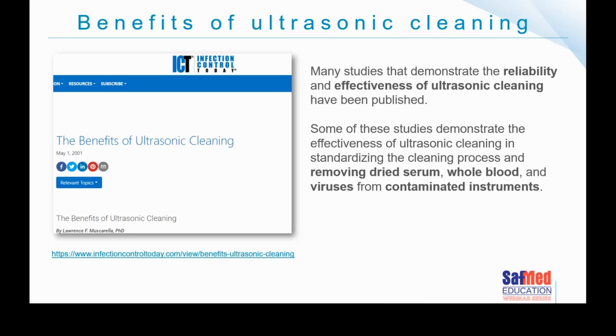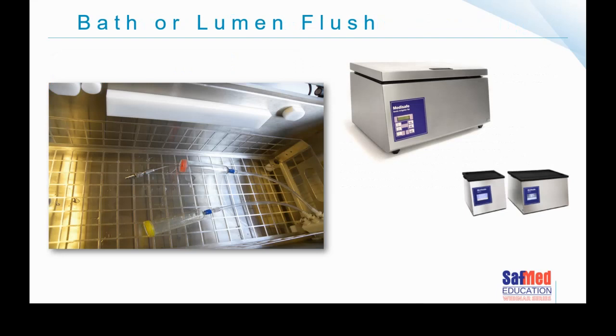I find that ultrasonic cleaners are probably one of the most underused pieces of equipment in the CSSDs, and it makes me very sad when I come into a CSSD and I see that the device is not well used. I have no way of advising how else to clean items like suctions that have complex lumens in them. A Yankauer sucker is a complex lumen. It's one of the items I included in my master's research. It runs at a different gauge inside of the device. It is incredibly difficult to get in there. No one-size brush fits in there. And the best method of cleaning items like that is with an ultrasonic flush. So an ultrasonic bath, but the bath itself has the ability to squirt through an ultrasonic flush as well.